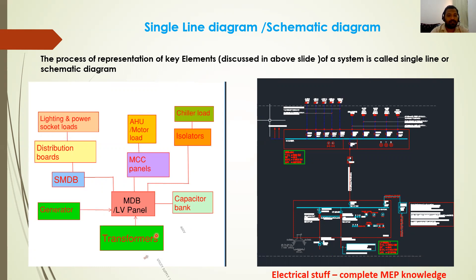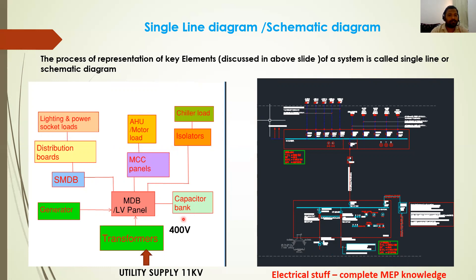The distribution transformers are step-down transformers — stepping down from 11 kV utility supply to 400 volts — feeding the main distribution board. The main distribution board also has a generator source, a capacitor bank to improve power factor, and feeds AC loads, motor loads, and lighting and power loads through SMDBs and distribution boards.